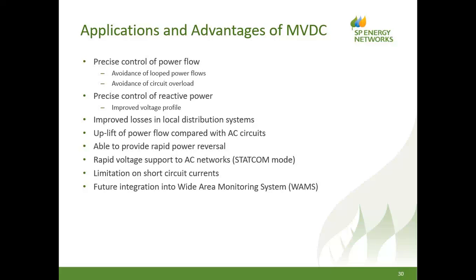So we designed this for 30 megawatts power. That's what it will do. It will not take an overload unless you tell it to, unless it is capable of doing so. So it will not become inherently overloaded by some looped power flow. We can precisely control the reactive power.